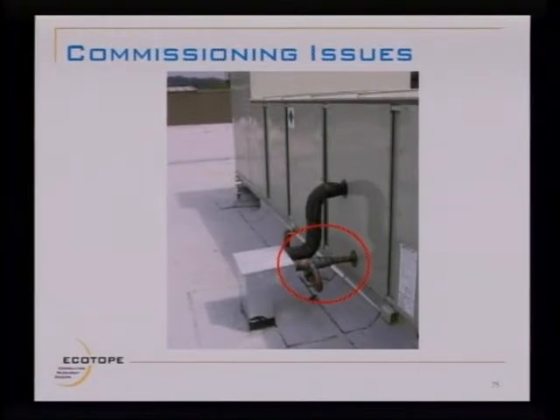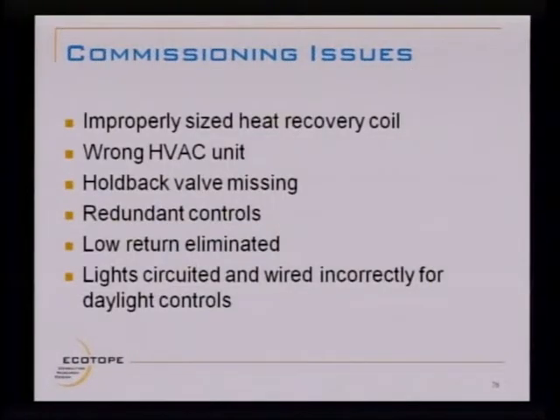So doing the commissioning on this store, a lot of issues came up. Some were more obvious than others. Some you can see when you're walking around, and others you have to dig and dig through the control system to see. This is an example. This is the refrigerant pipe coming up out of the roof, 2 1/4 inch pipe, necking down to a 3/4 inch pipe going into the side of the air handler. What happened there was that, again, the HVAC engineer didn't know anything about heat recovery.